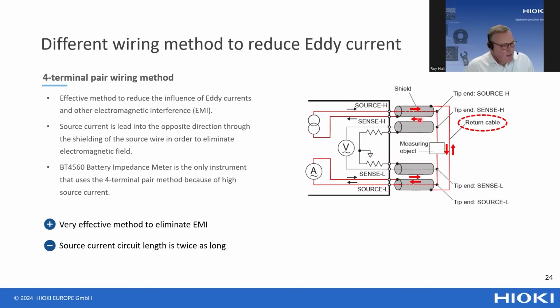So this is a very effective way. Why do we use this for this particular battery meter? It's because the test current of this BT4560 at the low range, the 3 milliohm range, is even higher than 1 amp—it's 1.5 amp. And if you don't take very good measures to control your magnetic flux, you will have influence on the measurement. So this method is very efficient for cancelling out electromagnetic induction.